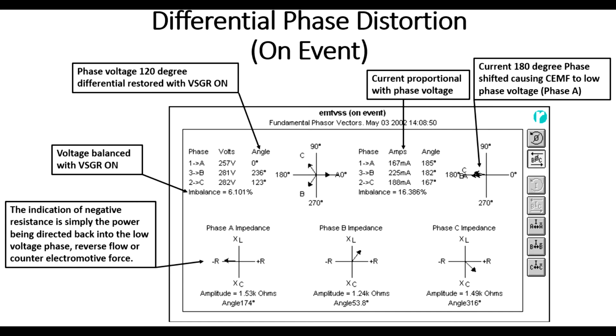And as we go to the right, you'll notice, how much energy did it take to fix that? Well, it was basically less than 1/4 of an amp. We'll see also to the right of that, all three currents are phase shifted to be 180 degrees out of phase with the phase voltage. As we remember, that's A, so the electrical vector for A is pushing to the right. The electrical vector for current is pushing to the left. We're pushing current back into phase A to push it back up to where it should be.